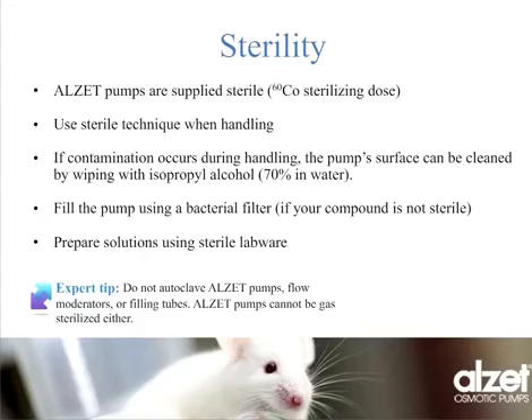ALZET pumps are always supplied sterile via a sterilizing dose of cobalt-60, and you should always use sterile technique when handling the pump. If the compound itself is not sterile, then you can fill the pump using a bacterial filter. If you feel like you've contaminated the pump through the course of handling it, we recommend that you clean the surface of the pump by wiping it with isopropyl alcohol. However, the pump or any of the pump components should not be sterilized via autoclave or gas.